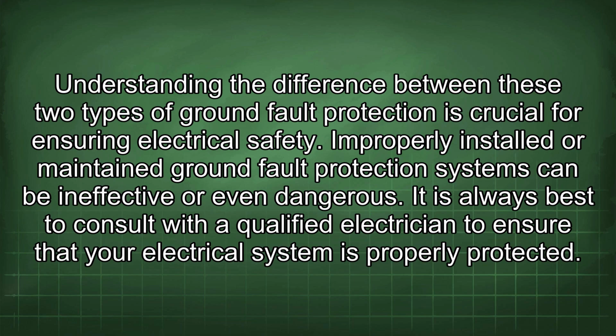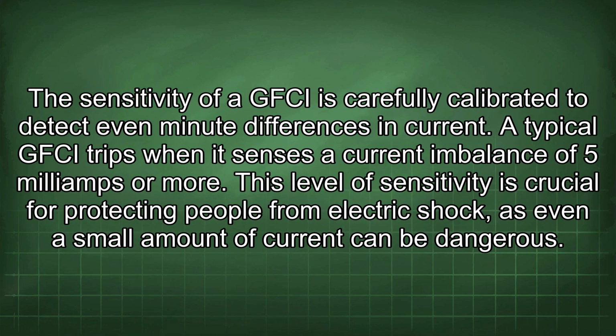Improperly installed or maintained ground fault protection systems can be ineffective or even dangerous. It is always best to consult with a qualified electrician to ensure that your electrical system is properly protected. The sensitivity of a GFCI is carefully calibrated to detect even minute differences in current. A typical GFCI trips when it senses a current imbalance of 5 mA or more.